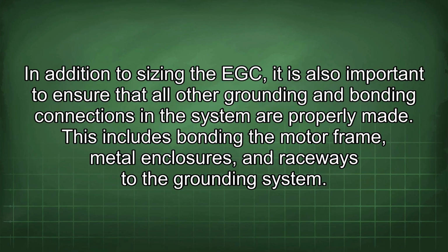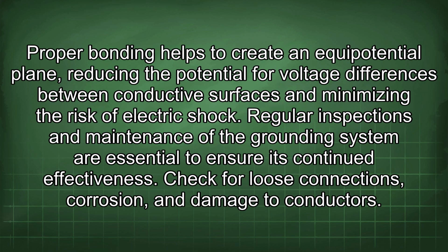In addition to sizing the EGC, it is also important to ensure that all other grounding and bonding connections in the system are properly made. This includes bonding the motor frame, metal enclosures, and raceways to the grounding system. Proper bonding helps to create an equipotential plane, reducing the potential for voltage differences between conductive surfaces and minimizing the risk of electric shock. Regular inspections and maintenance of the grounding system are essential to ensure its continued effectiveness.